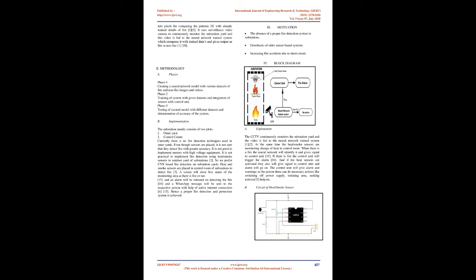The substation mainly consists of two plots: the outer yard and the control center. Currently there is no fire detection technique used in outer yards. Even though sensors are placed, it is not certain that they detect fire with greater accuracy, and it is not good to implement sensors with high voltage equipment. So it is not practical to implement fire detection using heat or smoke sensors in the outdoor yard of substations.